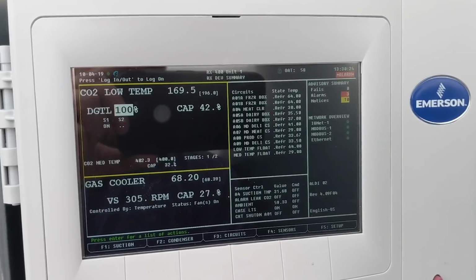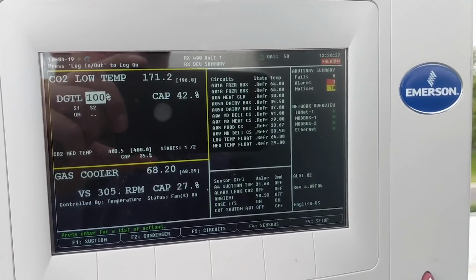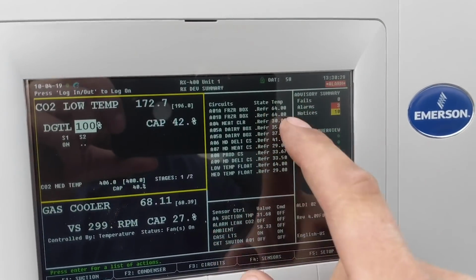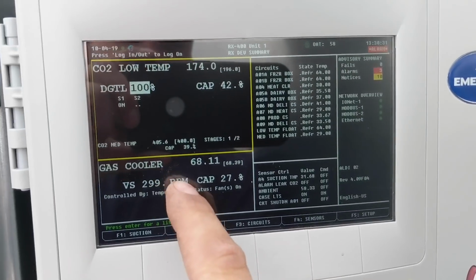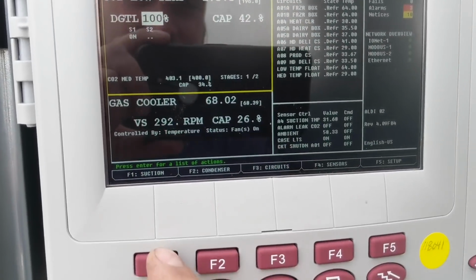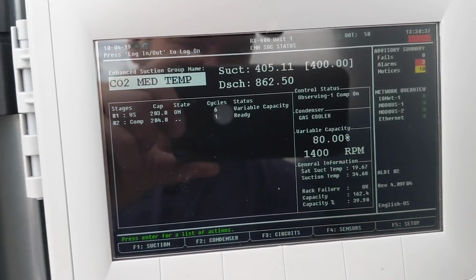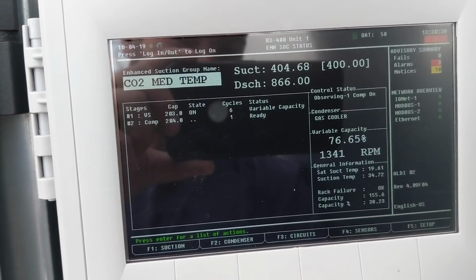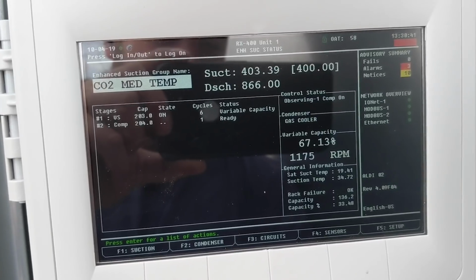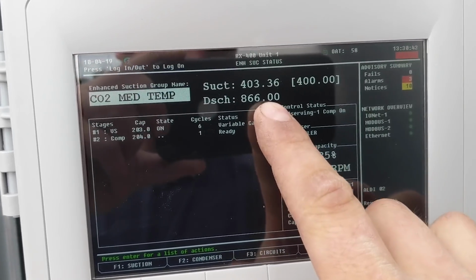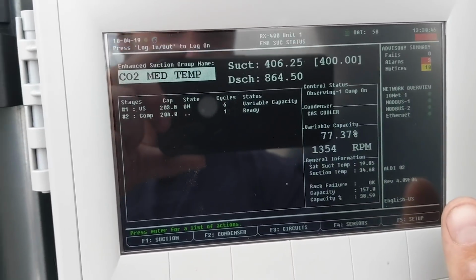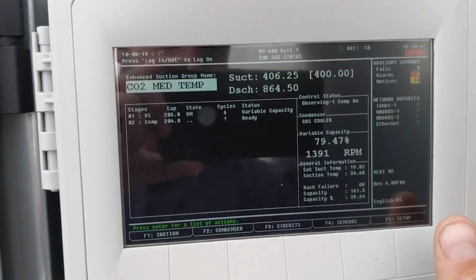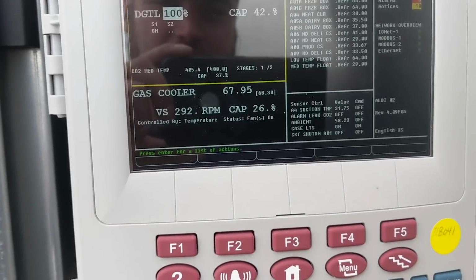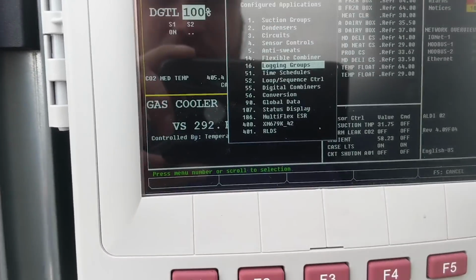So you can see you got your low temp suction group on there, all your case temperatures, your gas cooler sensors. So we got our medium temp suction on here with our variable capacity compressor going up and down. Discharges, we're running 866 pounds right now. We're running 400 pounds of suction pressure. And then in this door, we have all pulse valves.